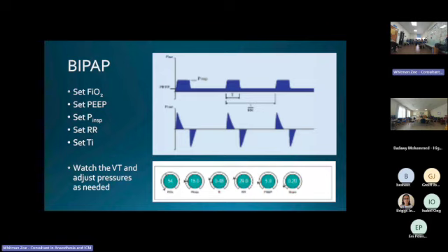If you look at the waveforms, it goes from your expiratory pressure and it goes up to your positive pressure. It's a very square waveform, so you don't get the peak in the same way. Your plateau pressure and your peak pressure are the same. And it will stay at that pressure for whatever inspiratory time you've set it at, or the ventilator's default. And the flow wave is a bit different as well. It will go up and then it will hold it open, but less air is going in, and then it will release it all in one go in a similar way the other one does.